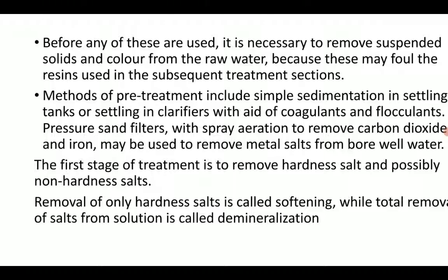Methods of pre-treatment include simple sedimentation in settling tanks or settling in clarifiers, and with the aid of coagulants and flocculants. Pressure sand filters, and spray aeration to remove carbon dioxide and iron, may be used to remove the metal salts from borewell water.